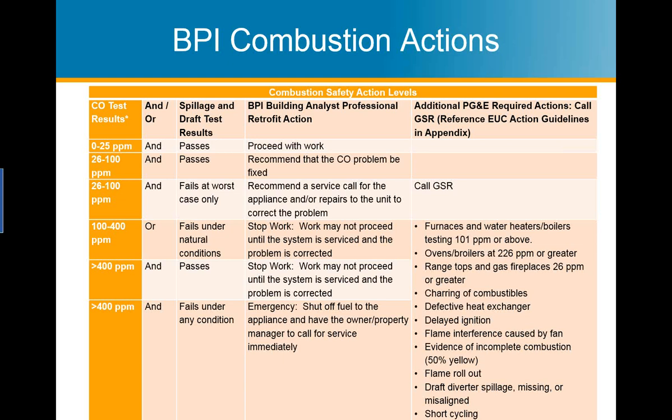Yeah, so we want you to test the CO alarm, but also there's an expectation that you have CO testing equipment with you while doing the site visit. That's a personal CO ambient monitor alarm, as well as a point CO combustion analyzer. So those pieces of equipment in conjunction should be able to tell you whether or not there is carbon monoxide present in the apartment, and then the test procedure can tell you whether or not the actual alarm mechanism of that piece of equipment is working. We should document that, though. So we'll put together the protocol, the expectation for what we mean when we say that a carbon monoxide monitor should be installed and working, and we will get that to the partner. Great. Thanks for that clarification.